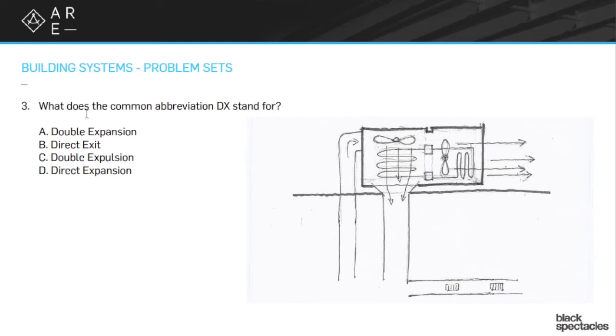But if that's appropriate to the type of tenants that you have, if that kind of turnover makes sense, then that's fine. The other big problem with this as a system is the way to make this work is I put a giant hole in my roof. So I have to get the air from that box down into the building. So instead of using those nice small water pipes with the chilled water in them moving around the building, I'm actually moving around with these huge big ducts and it takes up square footage. I have big holes in the roof. I have all these things that are sort of problematic with leaks and all those kinds of problems. So the right system for the right project. DX tends to be more typically used for projects that are more transient. I think it's probably the best way to say that so that things are going to move in and out. That's probably going to be a sort of logical choice. Other systems that are more like kind of institutional or something like that are probably going to be more associated with like chilled water systems, chillers where they have much longer lifespans, more centralized control over these pieces.